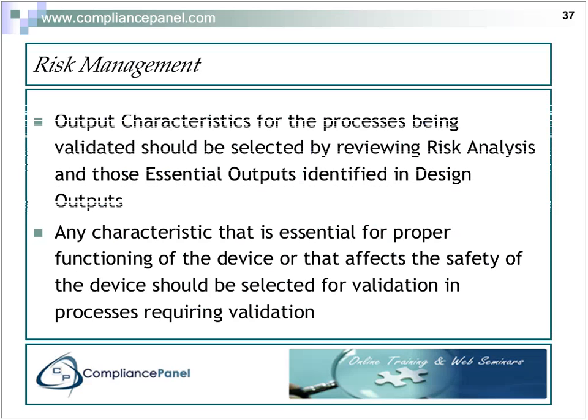Okay, risk management. That's a tool that's very important here. For the output characteristics of a process being validated, one of your selection criteria could be reviewing the risk analysis and looking for those items that were identified as risk control measures and those essential outputs identified in design output.